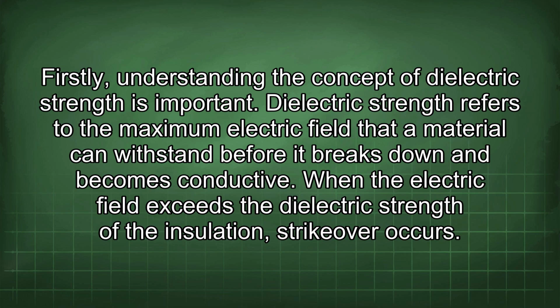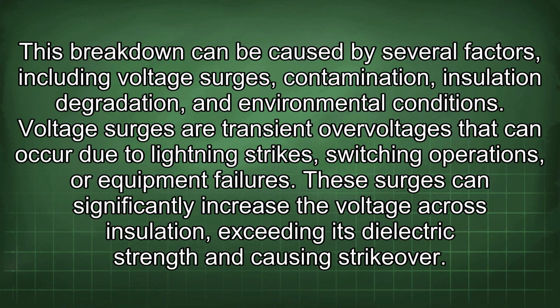Firstly, understanding the concept of dielectric strength is important. Dielectric strength refers to the maximum electric field that a material can withstand before it breaks down and becomes conductive. When the electric field exceeds the dielectric strength of the insulation, strikeover occurs. This breakdown can be caused by several factors, including voltage surges, contamination, insulation degradation, and environmental conditions.